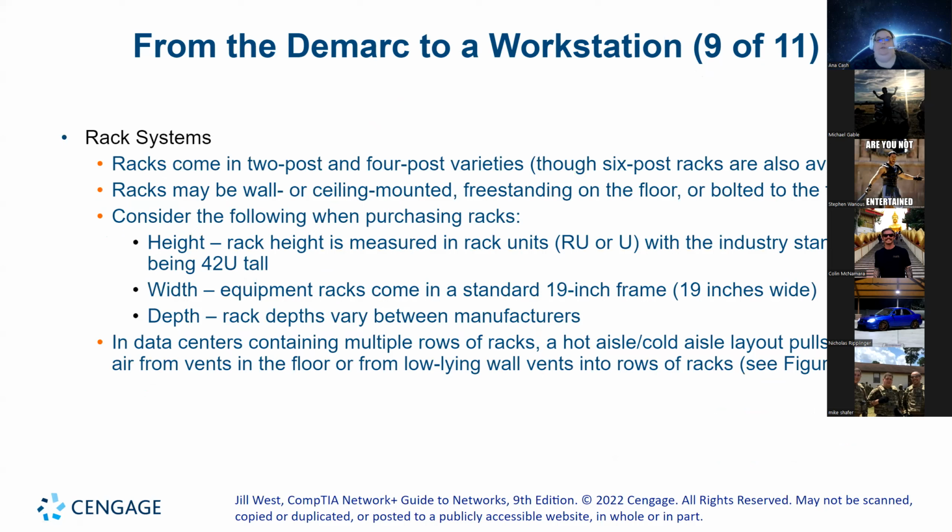So rack systems, they come in 2 or 4 post varieties. There are 6 post racks available too, but they're usually 2 and 4. They can be wall mounted or ceiling mounted, freestanding or bolted to the floor. And there are some things you need to consider when you're purchasing them. Height is measured in rack units or RU, with industry standard being 42 units tall. The width, equipment racks come in a standard 19-inch frame, and the rack depth varies between manufacturers. So that's one of those fun things you get to go look up.